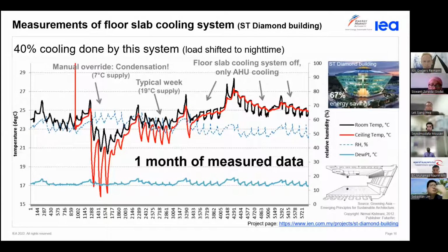Then they put it back to automatic, and then I think there were a lot of complaints maybe, then they switched off the system completely. So for the next 3 weeks over here, it's not switched on, and the building only operates on the air conditioning system. But of course that air conditioning system was only dimensioned to cater for about 60% of the load, because 40% of the cooling comes from this floor slab cooling system. So therefore you can see the black temperature, which is the room temperature, is higher than this typical week. So therefore it was a bit warm for those days.